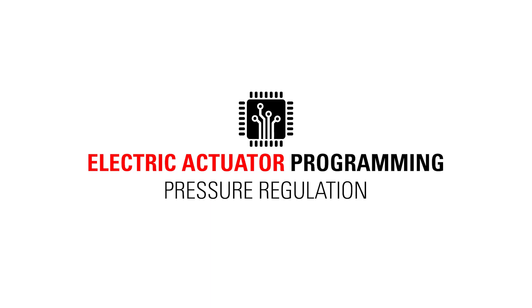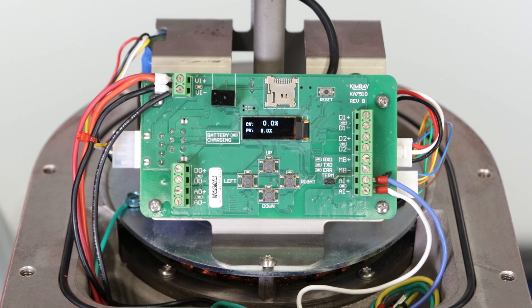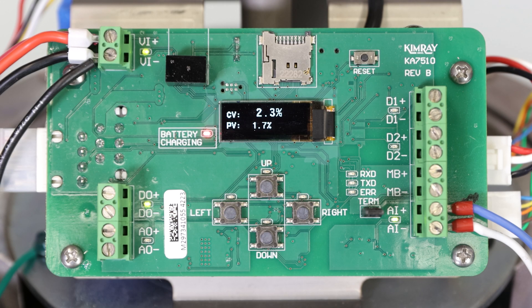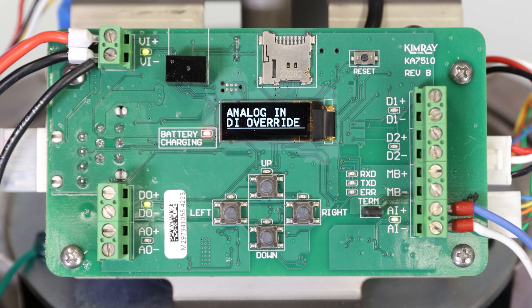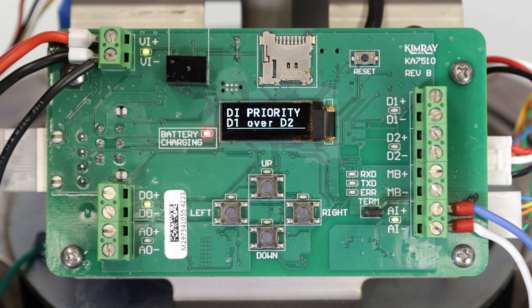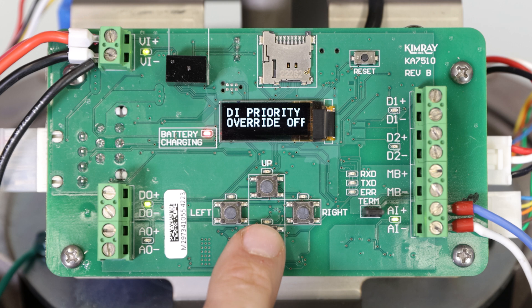Now we can select the set points on the electric actuator for back pressure regulation. First, we will adjust the control setup menu to tell the actuator what to do with each input. From the main operating screen, press right to get to the control setup menu. Press down to enter the menu, then press right again to select analog in DI override. This means we're controlling analog in and there's also a discrete override which is optional. Choose the best option for your application by pressing right to select it. This will take you to the next set of options to select your preferred discrete priority. We will select D1 over D2 and press right.